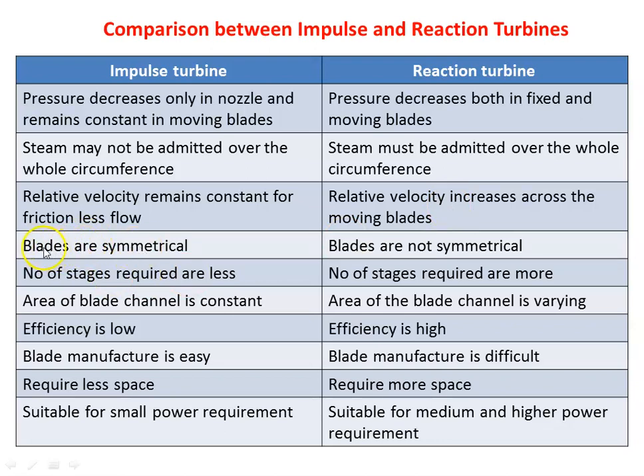In the impulse turbine, blades are symmetrical; in the reaction turbine, blades are not symmetrical. The number of stages required in the impulse turbine is less because the pressure drop and power generation per stage is higher; in the reaction turbine, more stages are required for the same power output. The area of the blade channel is constant in the impulse turbine but varying in the reaction turbine. Efficiency is lower in the impulse turbine due to higher exit velocity; in the reaction turbine, efficiency is higher. Blade manufacture is easy for the impulse turbine due to symmetrical blading, but difficult for the reaction turbine due to the aerofoil blade shape. The impulse turbine requires lesser space and is suitable for small power requirements, whereas the reaction turbine requires more space and is suitable for higher or medium power requirements.